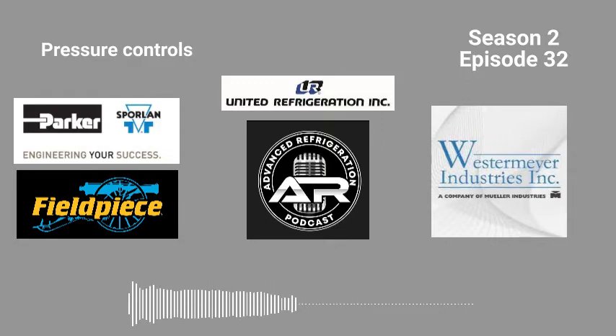Now we're going to go to the rack side with each compressor having its own individual low pressure control — this is the better option. Generally you see Hussmann do this with something called switchback. Switchback is basically a relay that bypasses the low pressure control. When you're in normal operation with the EMS running things, the relay is closed and you're bypassing around the low pressure control. This keeps it from fighting the EMS, which is the best option — now you can stage those low pressure controls so they're only in the loop if the controller fails.